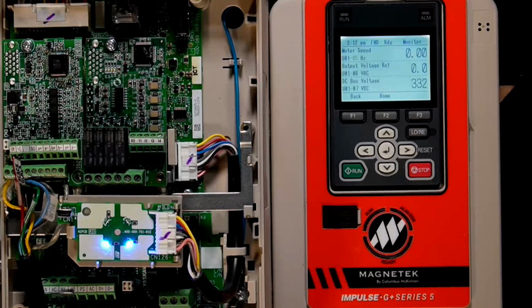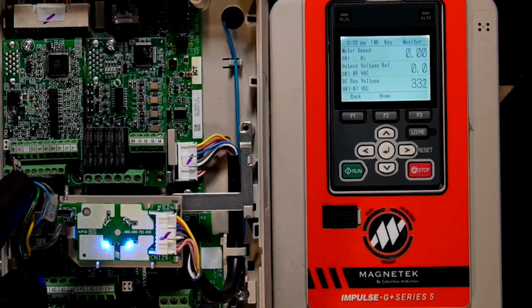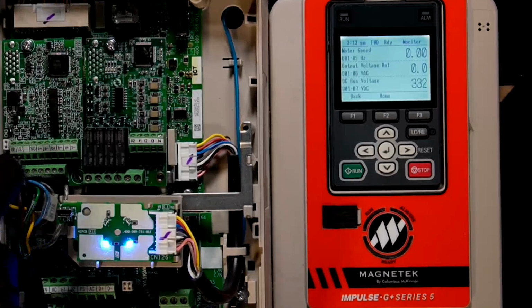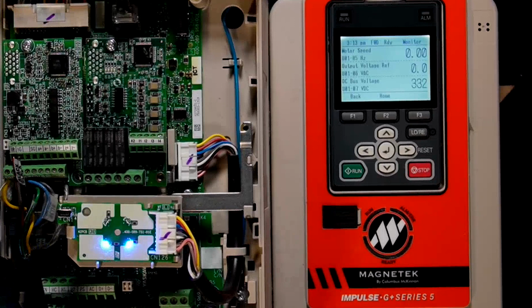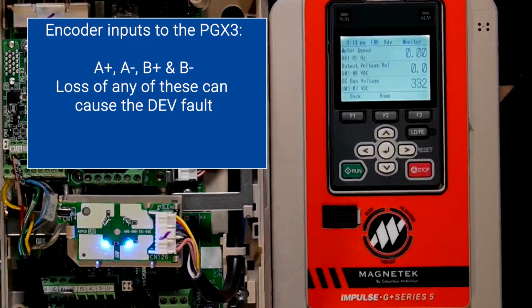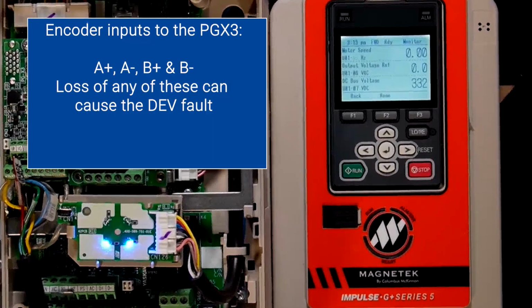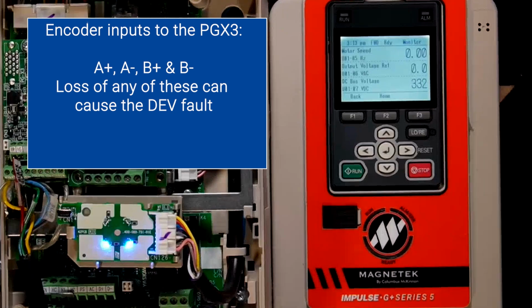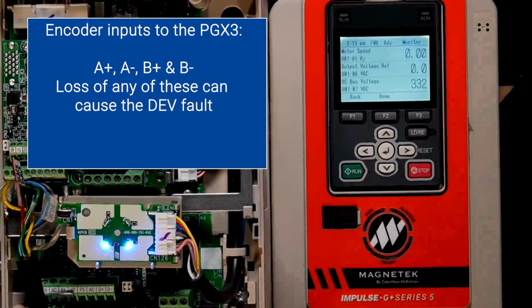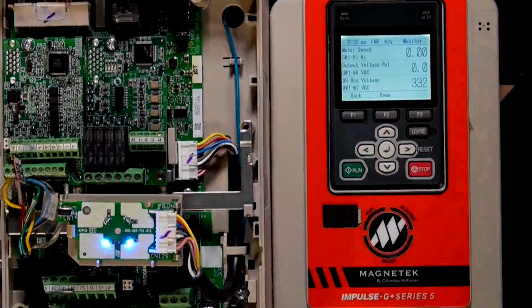I am going to demonstrate what happens when the drive trips out on an encoder signal related issue. So this is the PGX3 card here. For simplification, I am going to just remove one of the terminal inputs, the A+ input, to demonstrate the results of when we have an issue with the encoder signal.